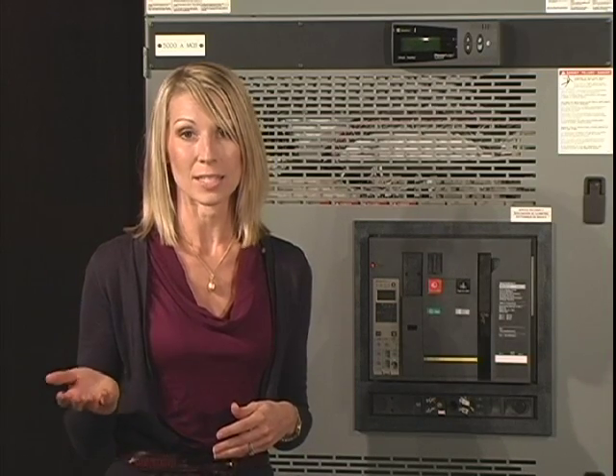The Masterpact M circuit breaker was sold primarily to OEM equipment builders in the late 1990s to early 2000s, and the circuit breaker applications were primarily used in paralleling switchgear, generator switching, and UPS output breakers. The current production Masterpact NW circuit breaker design affords the Schneider Electric Services Organization to offer these customers a cost-effective means to modernize the protective device without the need to replace the switchgear. This ultimately extends the useful life of the existing asset.